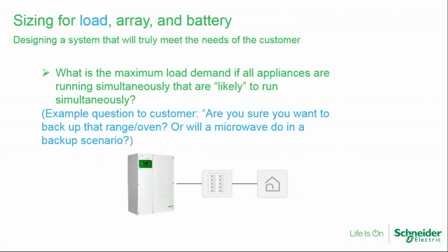But when you do the retrofit, you still want to size the system as though it was a storage-based system, which means that we need to have a good idea of what the loads are. Because the loads determine the size of the storage-based inverter, in this case, the XW. Peak load determines the size of the inverter. And then average load and runtime determine the size of the battery bank. And then the size of the battery bank determines the size of the array. Well, in an AC coupled system, the array is already determined pretty much. You might want to add some, but not very likely. But we still need to know loads and battery bank size.